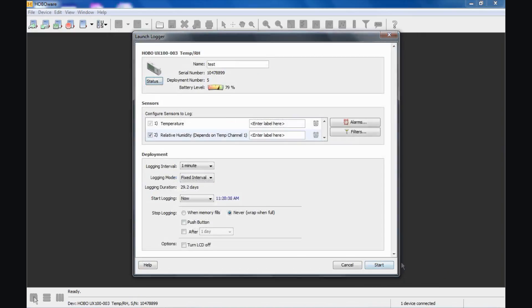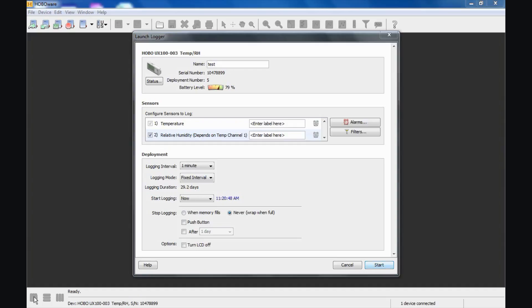Back in the launch window here, it is important to understand that these values that are being populated in this screen for the name, the sensor selected, the logging interval, things like that, these are being obtained from the previous launch. So however the logger was launched before, this is how this is being populated and it gives you the ability to change it or just launch this logger again with the same configuration.